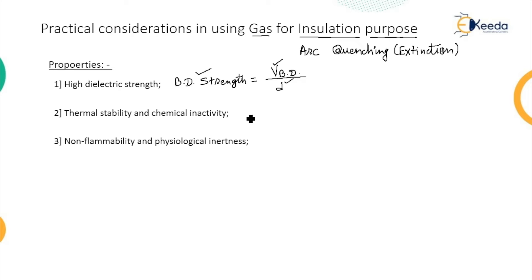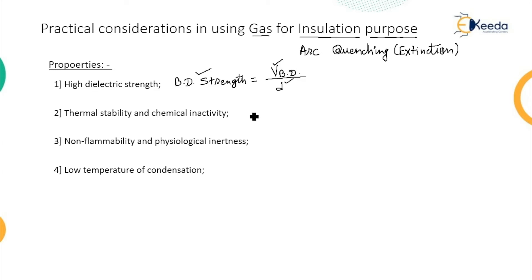Another point is physiological inertness — whenever the gas encounters changes in parameters, it should not affect the heart and hemoglobin of the operator or person. So it should be non-toxic and non-anesthetic. It should also have a low temperature of condensation, meaning the conversion of gas into liquid should occur at a low temperature. Additionally, it should have good heat transfer capability, especially during the formation of an arc.